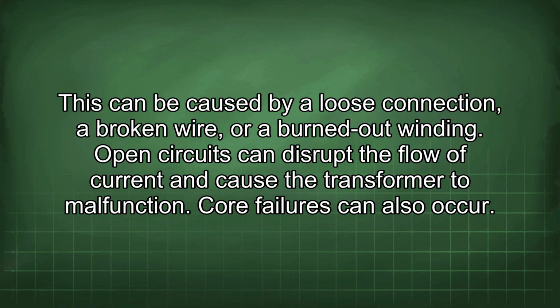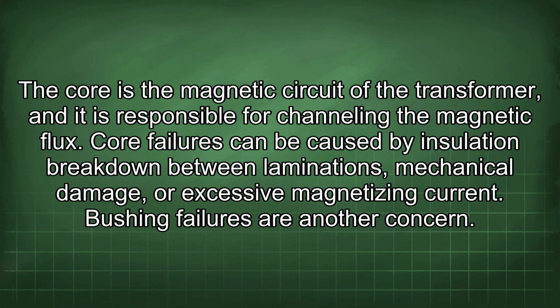Core failures can also occur. The core is the magnetic circuit of the transformer, and it is responsible for channeling the magnetic flux. Core failures can be caused by insulation breakdown between laminations, mechanical damage, or excessive magnetizing current.